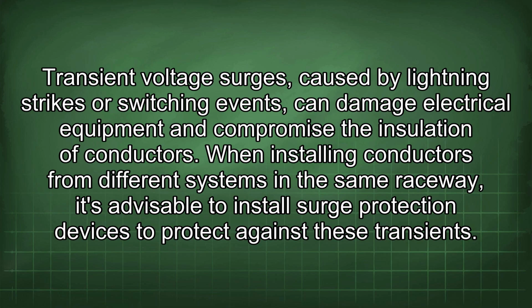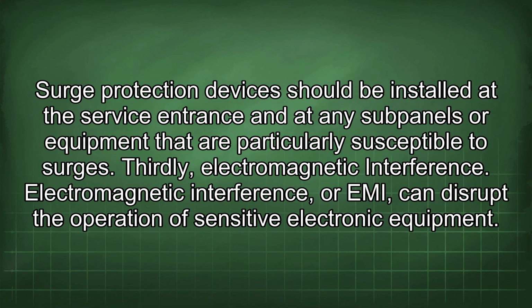Secondly, surge protection. Transient voltage surges caused by lightning strikes or switching events can damage electrical equipment and compromise the insulation of conductors. When installing conductors from different systems in the same raceway, it's advisable to install surge protection devices to protect against these transients. Surge protection devices should be installed at the service entrance and at any subpanels or equipment that are particularly susceptible to surges.